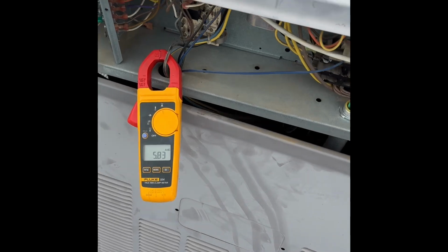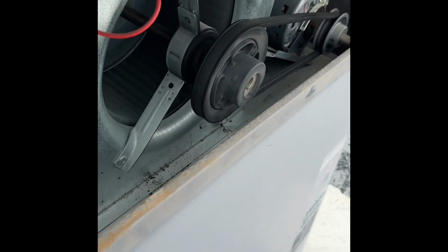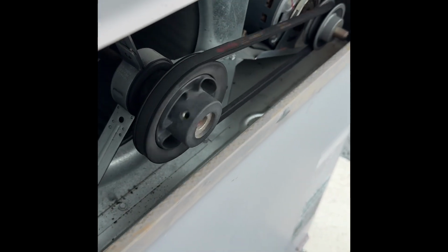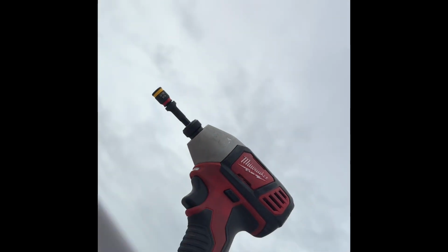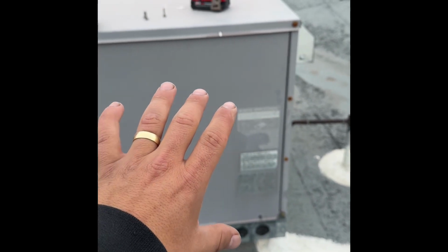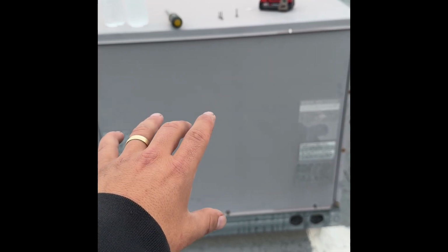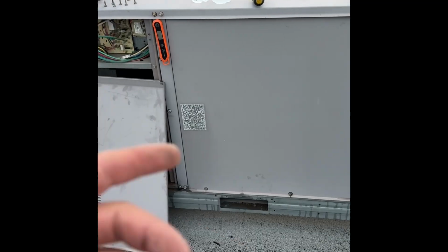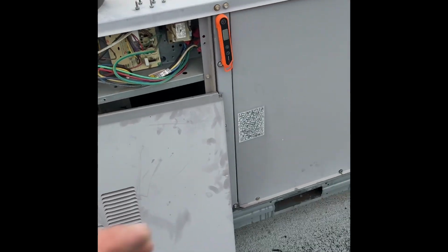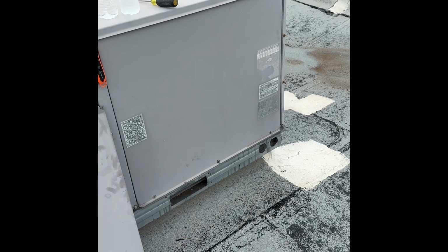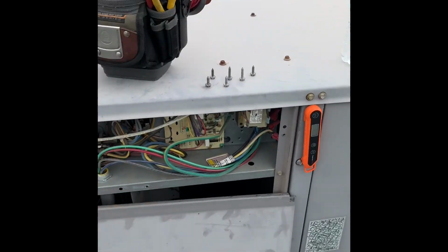So amp draws. Again, visual inspection on your blower. Check it in operation. Make sure your belt's not bouncing. Make sure your pulleys are aligned. Right? Very important. So that looks good. And because of overamping concerns, you don't want to leave this exposed for too long for the blower motor, because it's going to run at higher amps because of airflow issues. So check it visually, then just close the panel up. Let's save the screws for later, right?